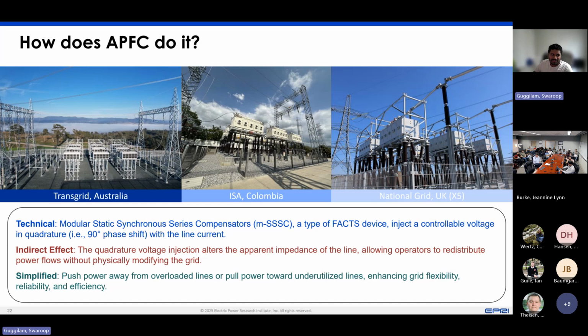In simplified terms, it's dynamically changing the apparent or line impedance. If you increase the impedance, you're resisting, so less power flows through it; if you reduce it, you allow more power to flow. Bottom line: this APFC device lets you push or pull power on a particular transmission line wherever it's installed—that's the key takeaway.